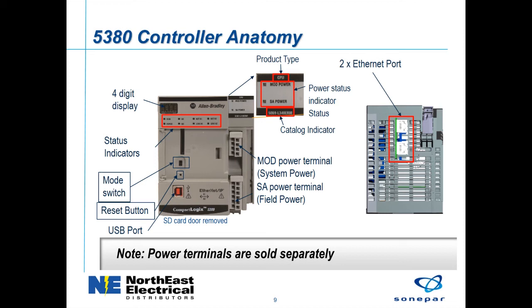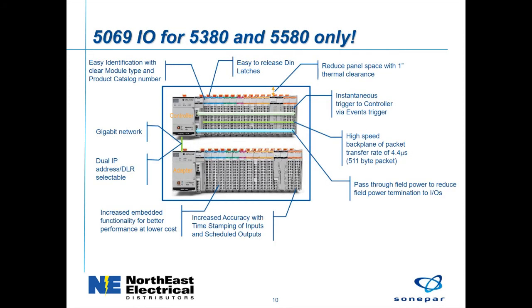So along with the new 5580 and 5380 controllers, there's a new I/O platform that goes with them. It is not backwards compatible. You cannot use this with 5370 or 5570 controllers or earlier. It's only for the 5380 and 5580 controllers. It's a smaller footprint than our existing Compact I/O. It's about, I think, 60% of the size.